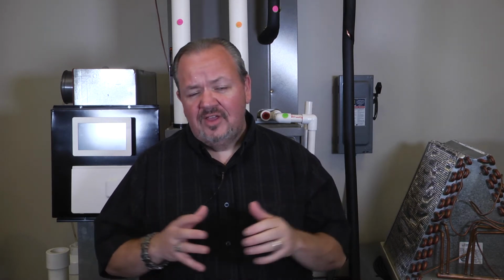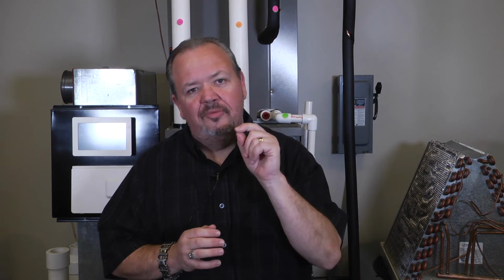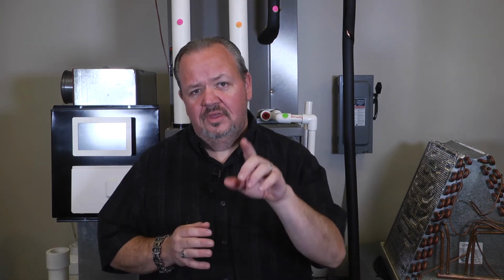Our residential duct design class starts with the fundamentals of duct design and airflow, shows them how to calculate the proper friction rate, apply that friction rate to a duct calculator, size out a duct system, and determine if an existing duct system is the problem. Let's be realistic, 80% of the time the system's not the problem, it's the application and design of the ductwork. If we can teach them how to design, develop, or fix it, how much better of a technician are they for you?